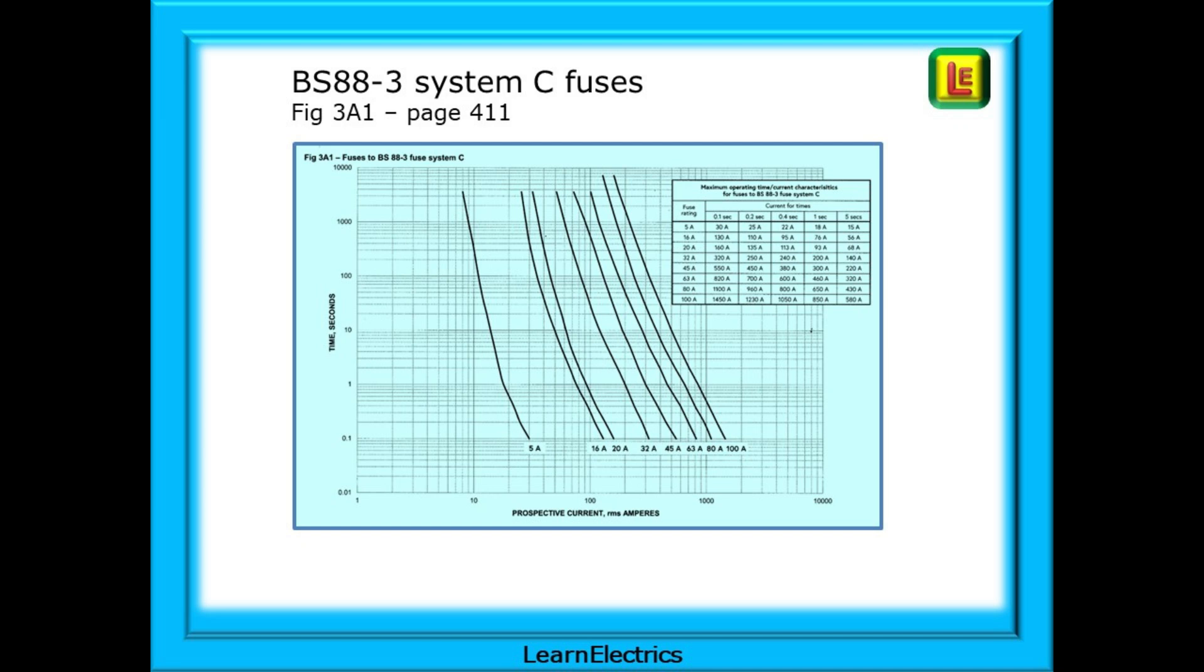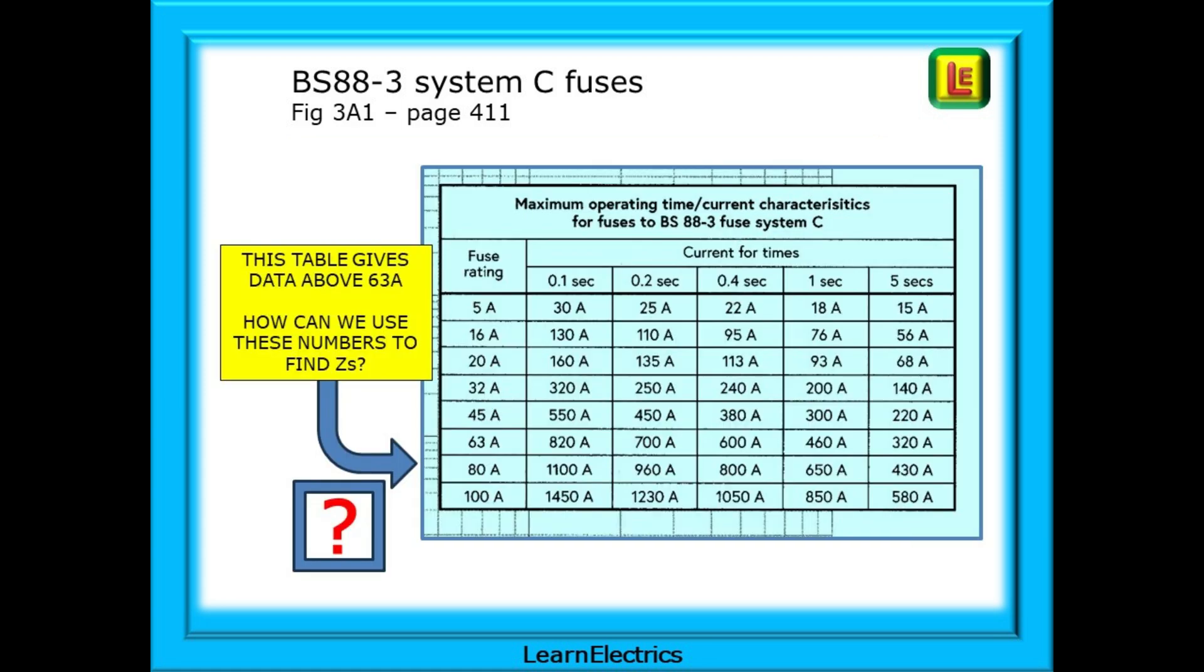Turn now to page 411 of the book. This is figure 3A1 and shows the current and time curves specifically for BS88-3 system C fuses. These are sometimes called the response curves or tripping curves and each fuse type will have its own unique curves. Of most help to us is the chart shown at the top right. This table lists data values above the 63 amps shown on page 67. And the 80 amp fuse that we need data for is shown here. But these are not ZS values. They are the amount of fault current that must flow in order that the fuse disconnects the supply in the required time. How can we use these numbers to find ZS?